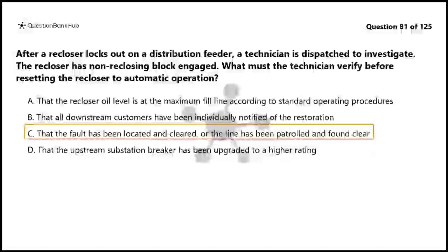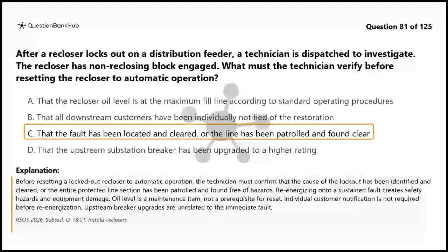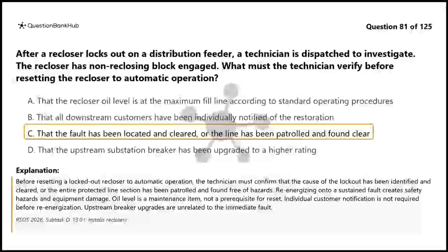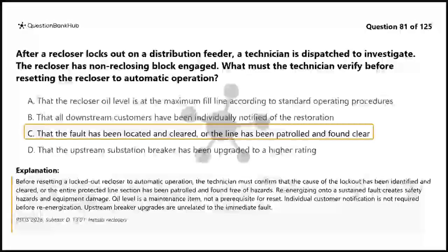The correct answer is C. Before resetting a locked-out recloser to automatic operation, the technician must confirm that the cause of the lockout has been identified and cleared, or the entire protected line section has been patrolled and found free of hazards. Re-energizing onto a sustained fault creates safety hazards and equipment damage. Oil level is a maintenance item, not a prerequisite for reset. Individual customer notification is not required before re-energization. Upstream breaker upgrades are unrelated to the immediate fault.